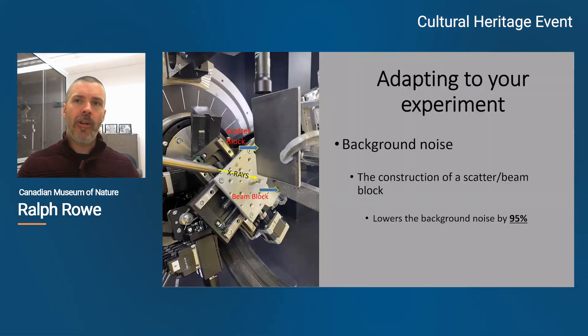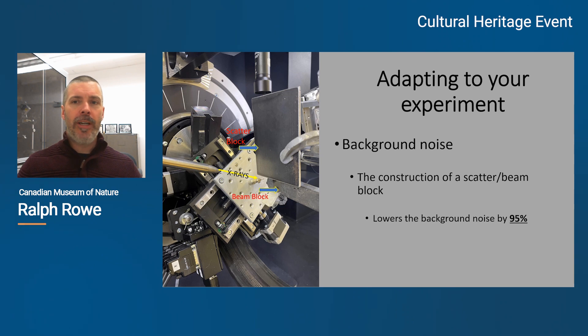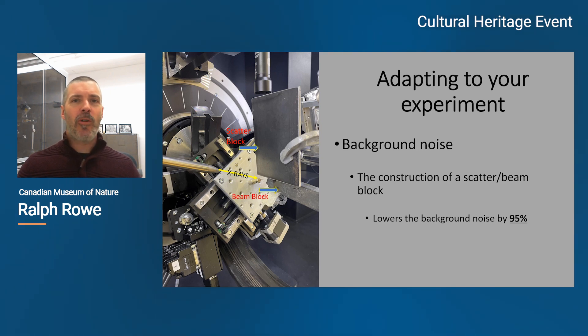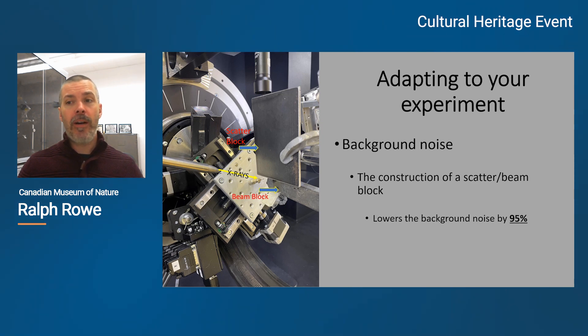As I mentioned earlier, I had dreams of fitting a beam and scatter block into my experiment. I wanted to reduce the background noise caused by the XRD experiment. The flexibility of the unit allowed me to do that by moving the sample stage into a more vertical setting, which allowed me to slide in the beam and scatter block that I had built. The results were really conclusive — it lowered the background noise by 95%.